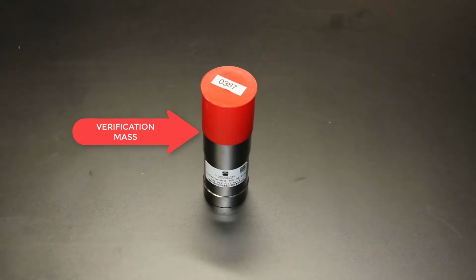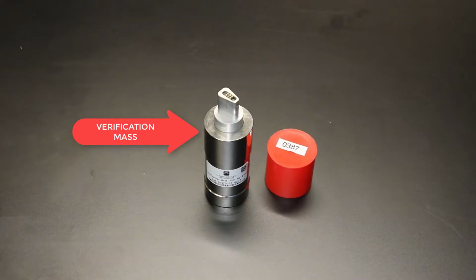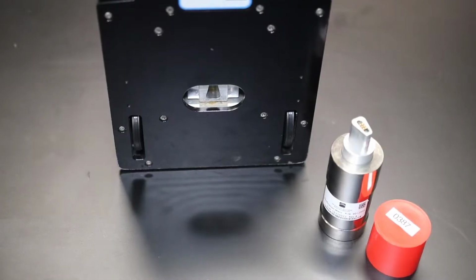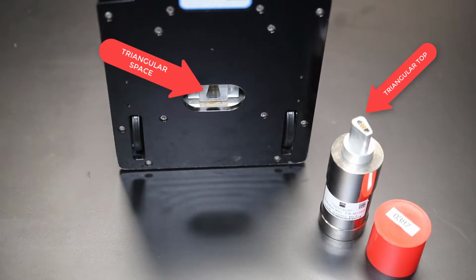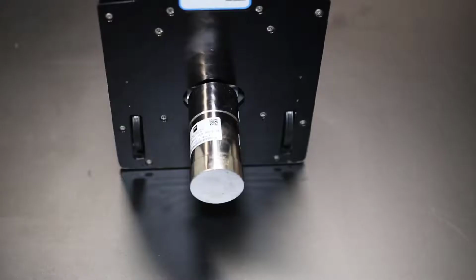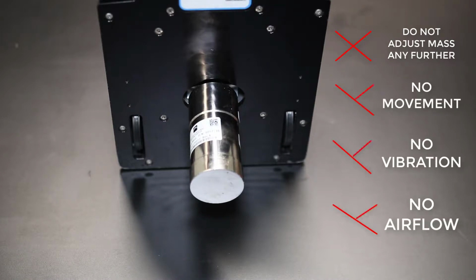Take the cap off the verification mass. This will be inserted into the BOT in the same space that a sensor will later. Insert the triangular top of the verification mass into the corresponding space on the BOT. Do not adjust the mass any further once you have placed it inside the BOT. It is important to be aware that the verification process will not work if there is any movement, vibration, or even airflow around the device.